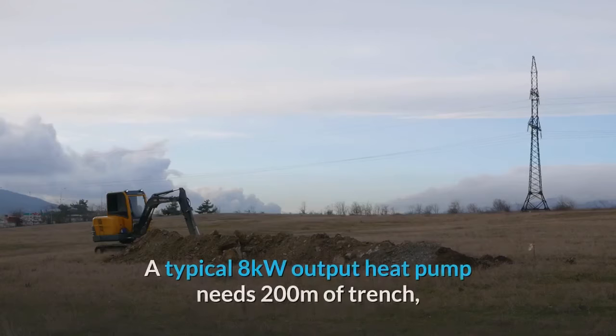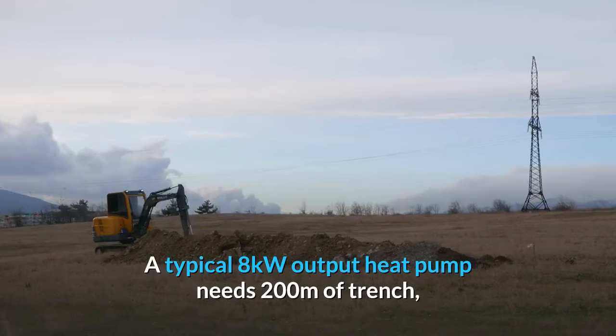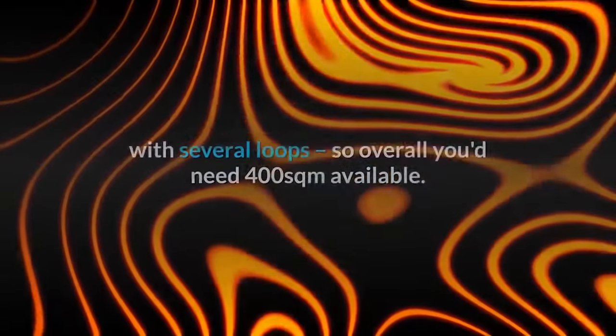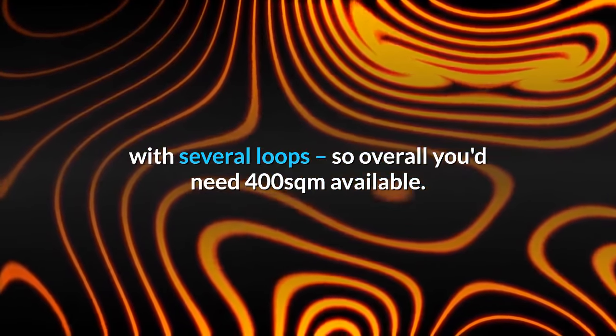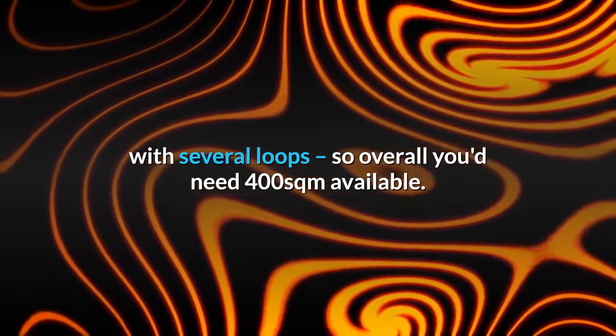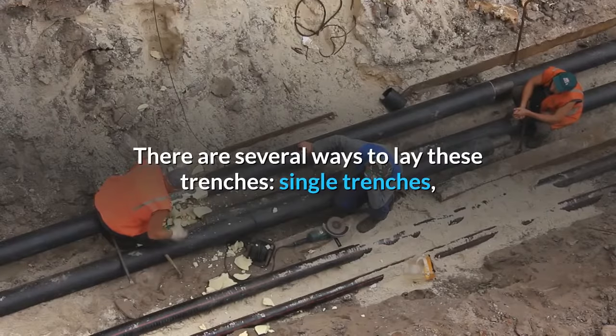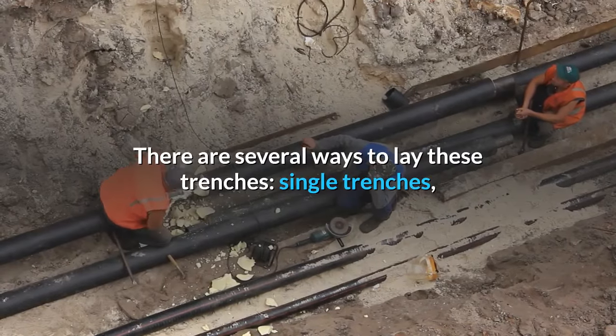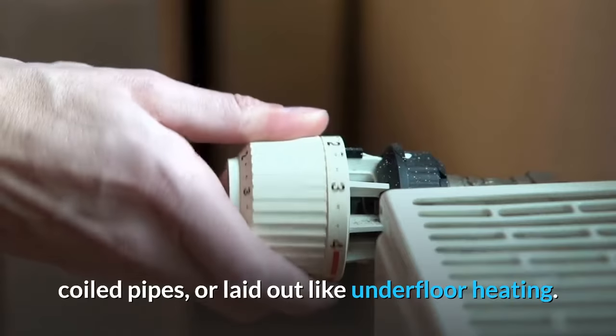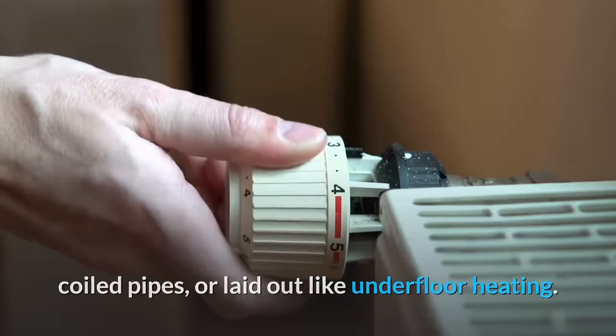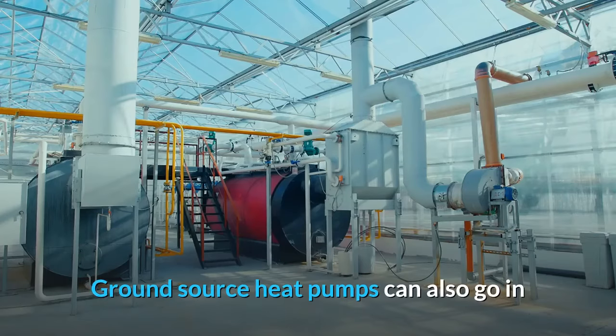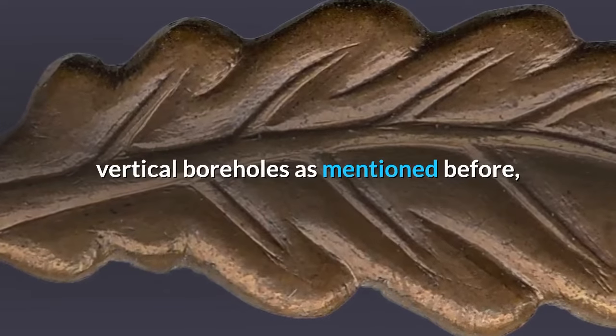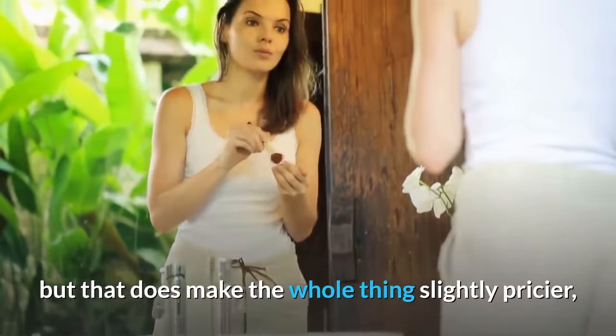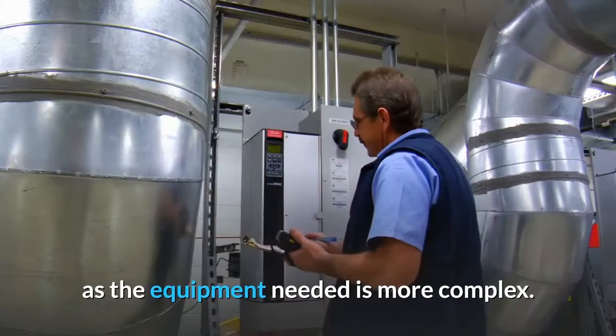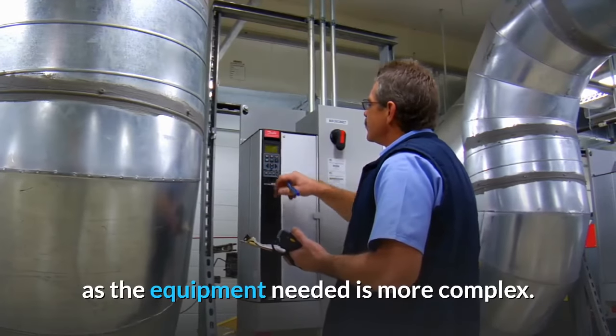First of all, with a lot of digging. A typical 8 kW output heat pump needs 200 meters of trench, with several loops, so overall you'd need 400 square meters available. There are several ways to lay these trenches: single trenches, coiled pipes, or laid out like underfloor heating. Ground source heat pumps can also go in vertical boreholes, but that makes the whole thing slightly pricier, as the equipment needed is more complex.